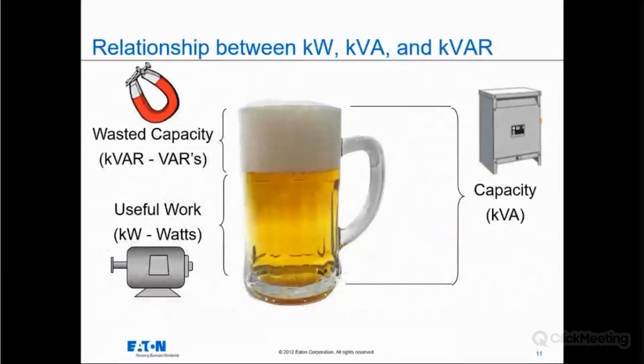An even more simplistic way to think about it, and maybe even funny or comical, is to think of a beer mug. If the beer mug is the transformer sitting out in front of your facility, you are currently pulling some ratio of beer and foam through your mug, or through your transformer. Would you rather have a lot of foam, or wasted capacity in terms of kVAR in comparison to watts? No, you would probably prefer to have more beer, or more kW, in that mug than there is foam. You would be using that mug much more efficiently. The same thing applies to transformers. If you have a larger ratio of kilowatts versus kVAR, you're using that transformer in a much more efficient fashion.